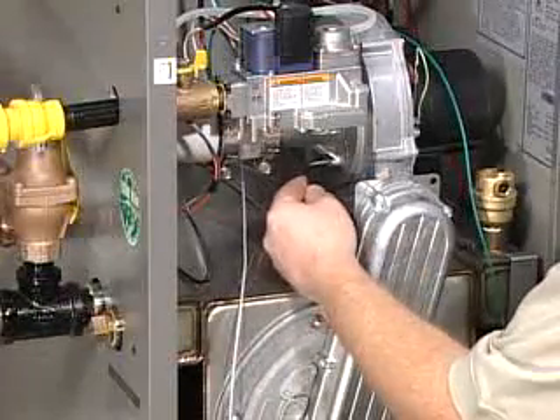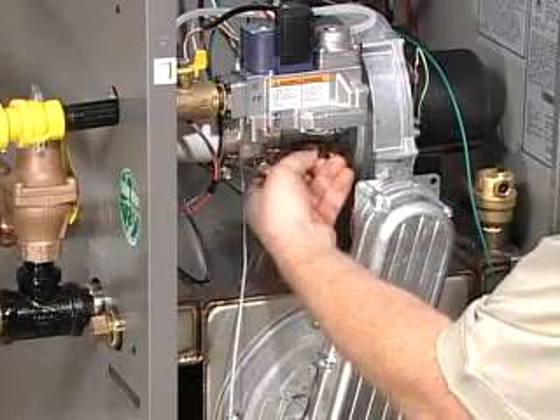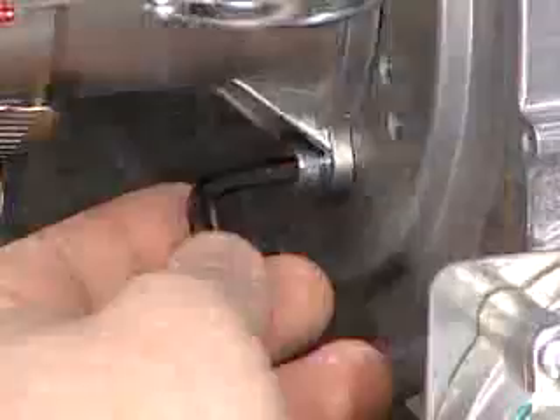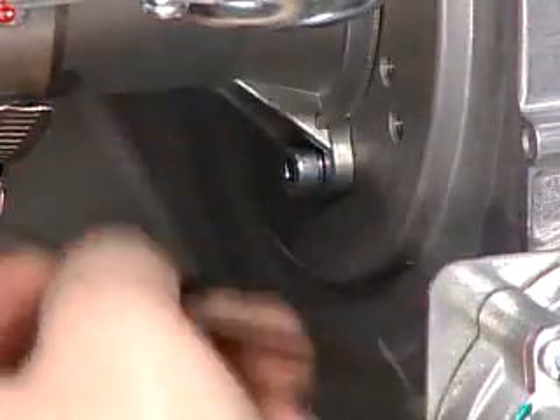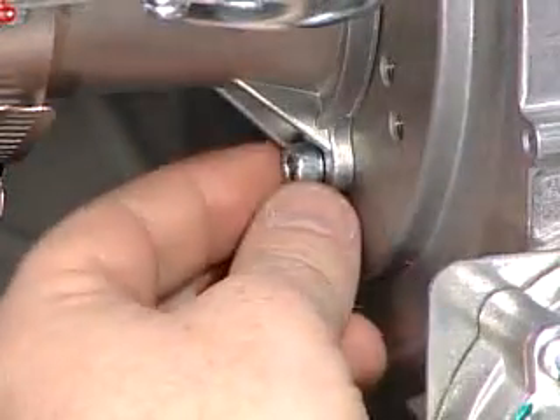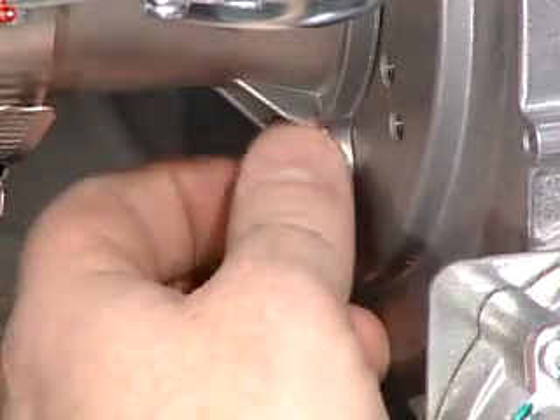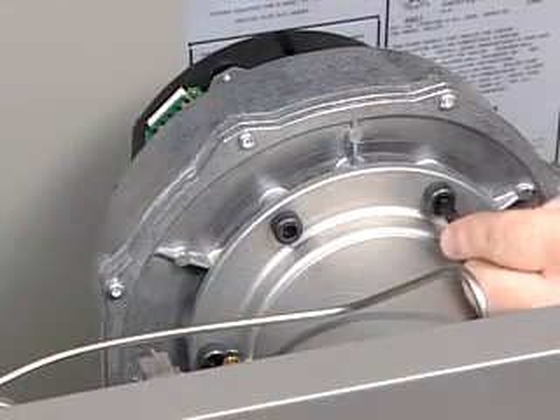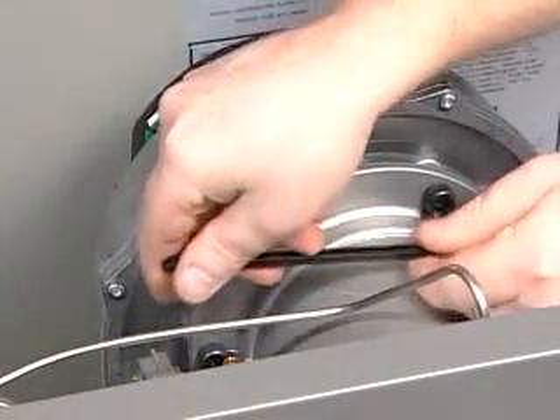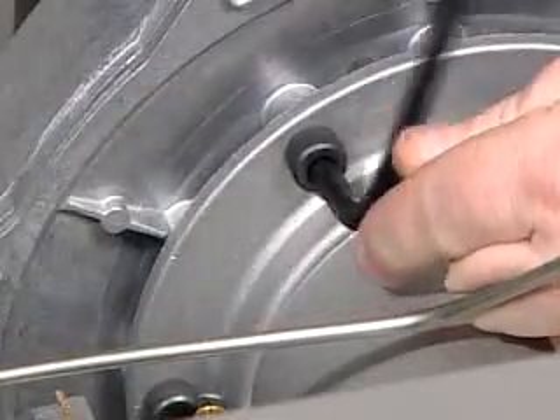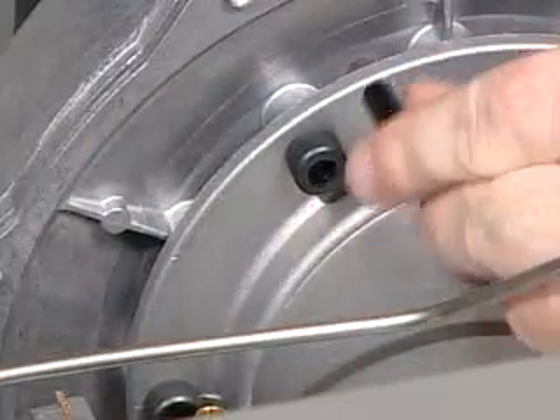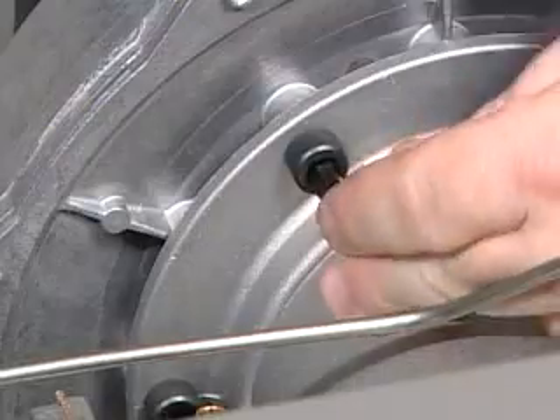For models 80 through 285, use a 4 mm Allen wrench to remove the screws securing the gas valve venturi to the inlet of the combustion blower. For 399 and 500 models, use a 6 mm Allen wrench to remove the screws securing the gas valve venturi to the inlet of the combustion blower.